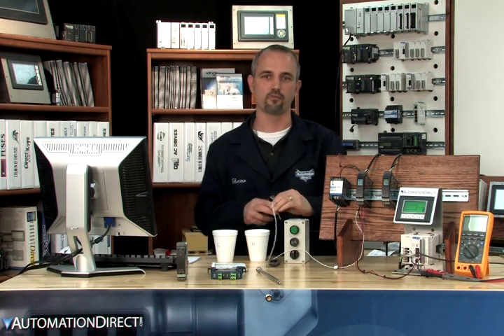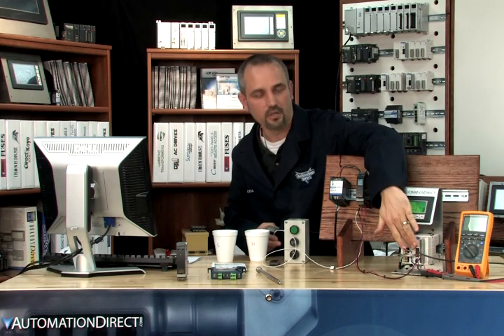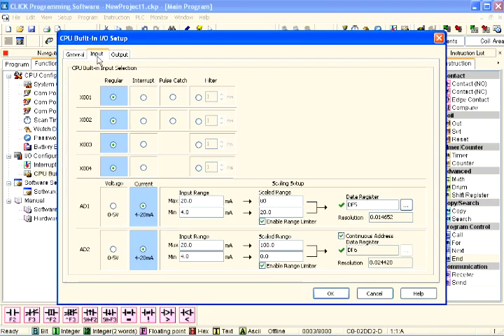Next, we're going to wire two wires from our signal conditioner to the input of our Click PLC. All we needed was the wiring diagram that came with the signal conditioner and the wiring diagram for the Click analog PLC. And last, we have two wires going to our green indicator light with a positive voltage wired directly to the light while we're switching the negative voltage to the light. What's nice about our Click PLC is that you don't have to write any code to set up the analog signal — we simply go to the CPU built-in I/O setup, select the input tab, and then select 4 to 20 milliamps.